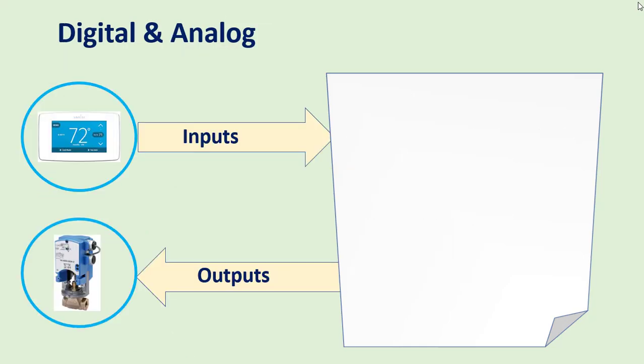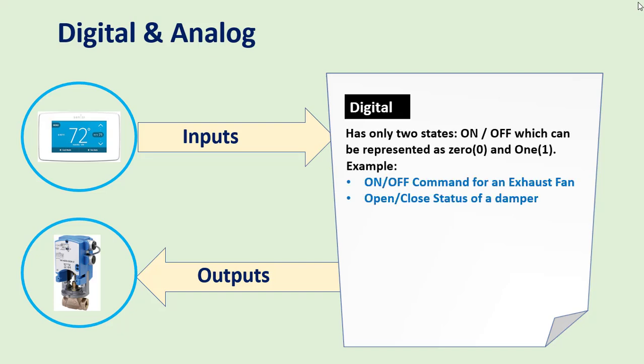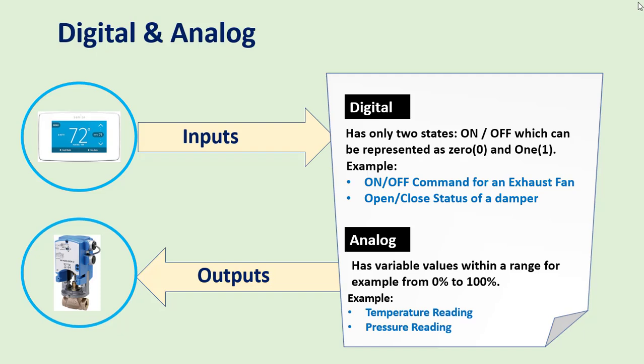Inputs or outputs to a control system can be either digital or analog. A digital signal has only two states — either on or off, represented as 0 and 1. An example is an on/off command for an exhaust fan or open/close status of a damper. An analog signal has variable values within a range, for example 0 to 10 volt or 4 to 20 mA. Examples include temperature readings from a temperature transmitter, pressure readings from a pressure transmitter, or a 0 to 10 volt control signal to a damper or valve actuator.